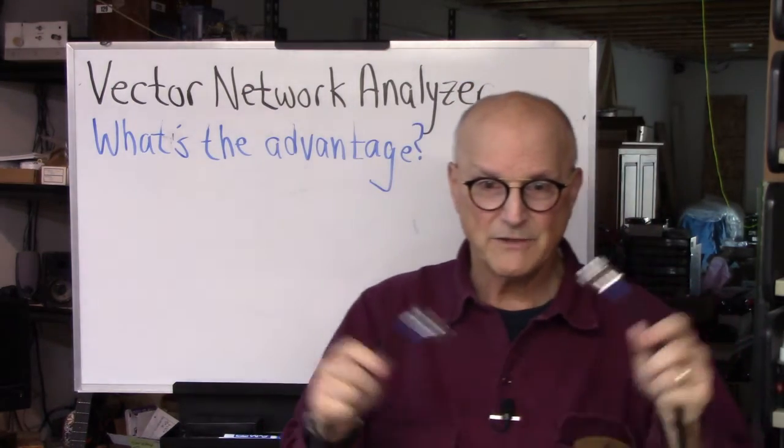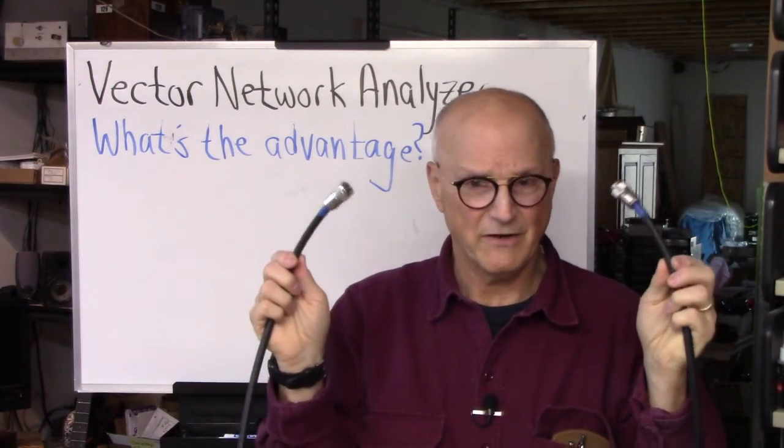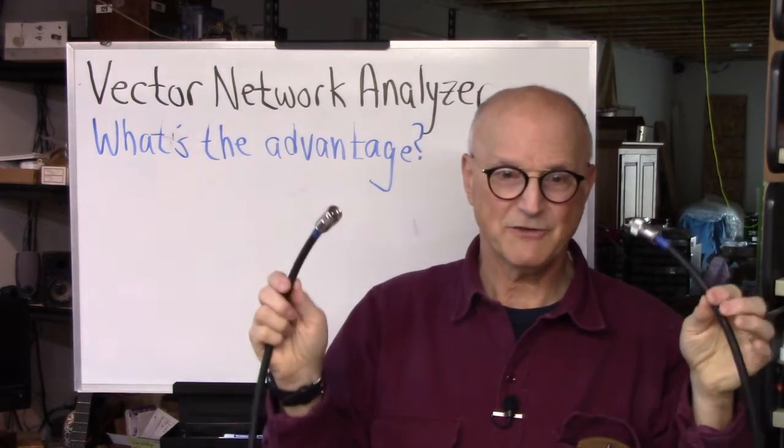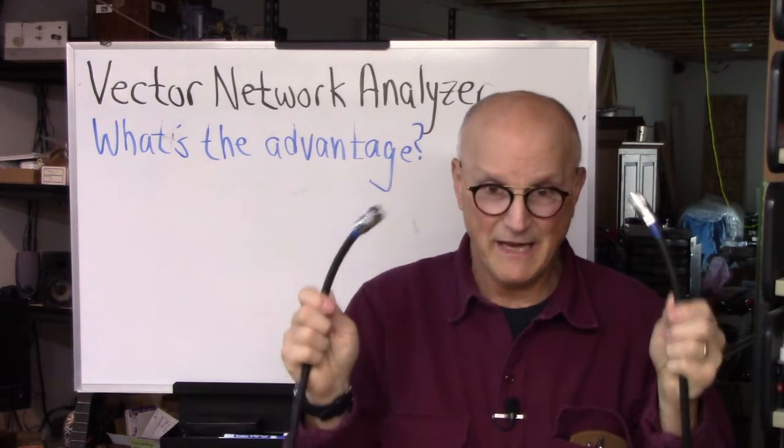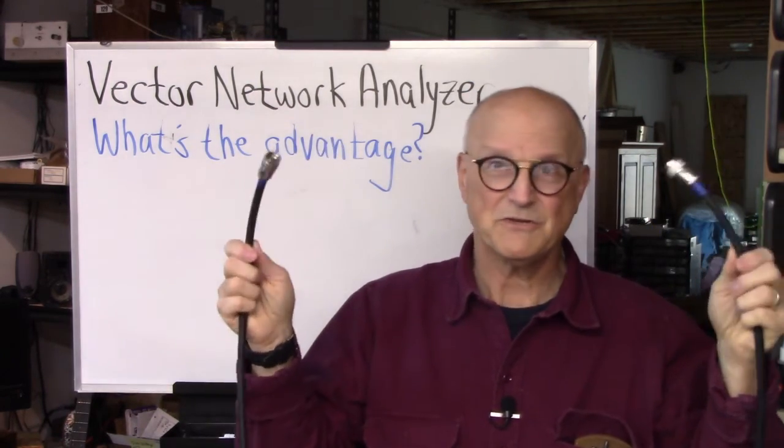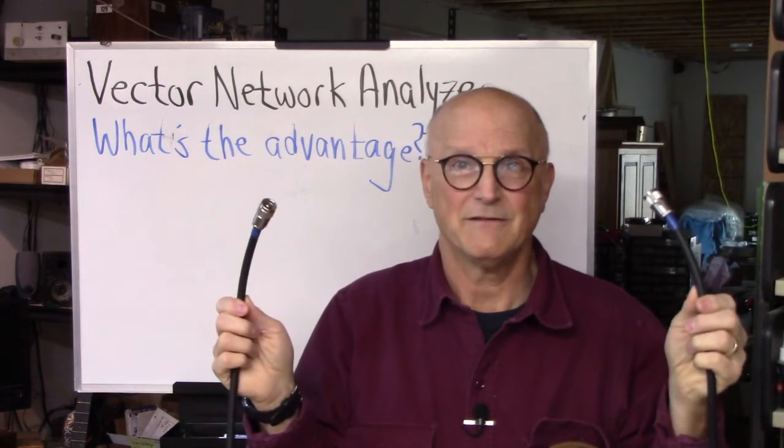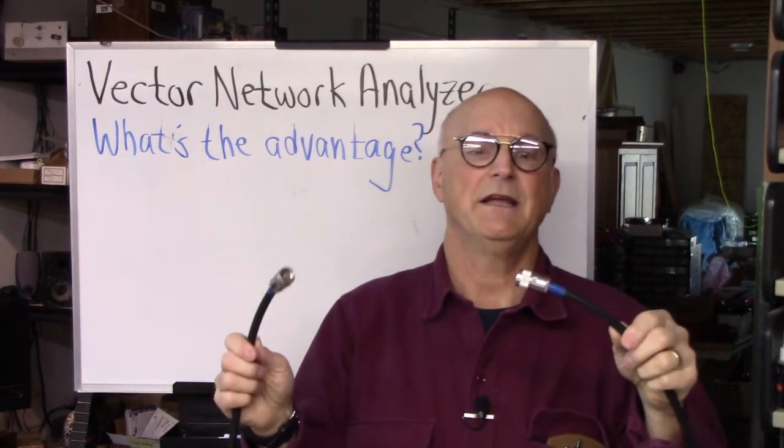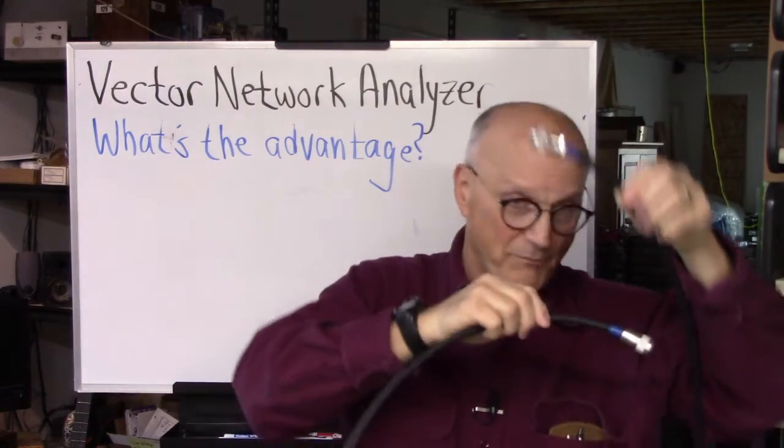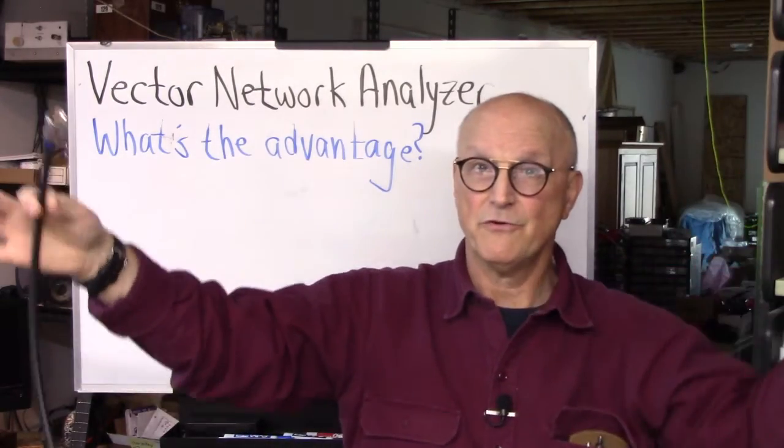So, if you're measuring the impedance of a device, connecting your test instrument by way of a cable, you're just going to get the wrong answer. Because you're going to see the transformed impedance as it goes through your cable.